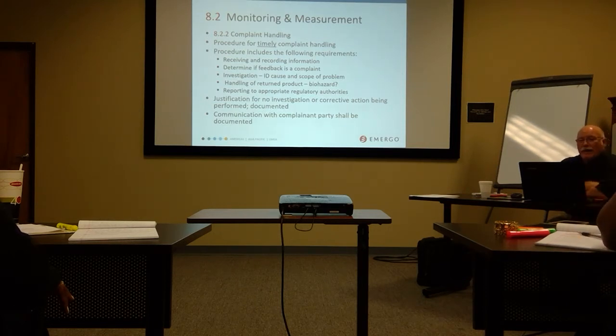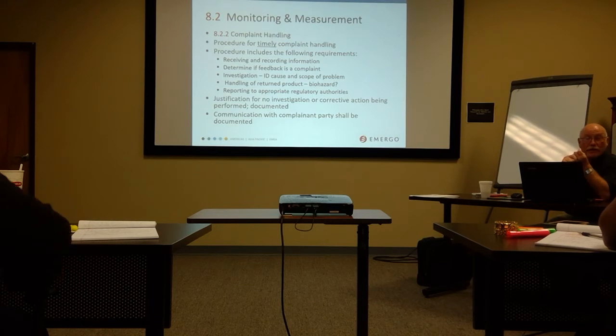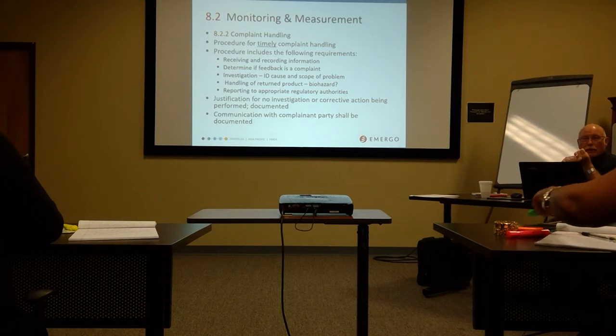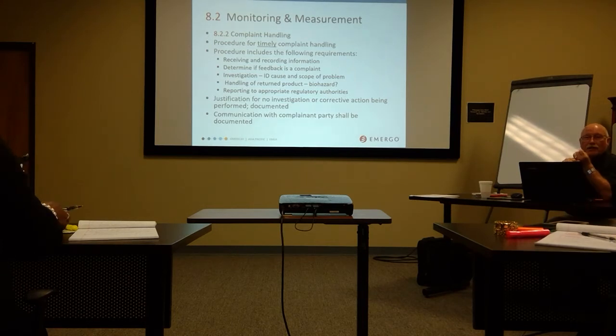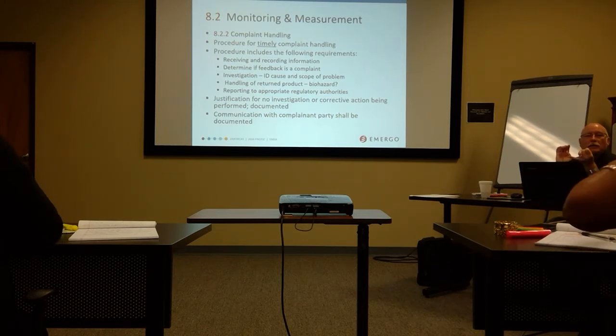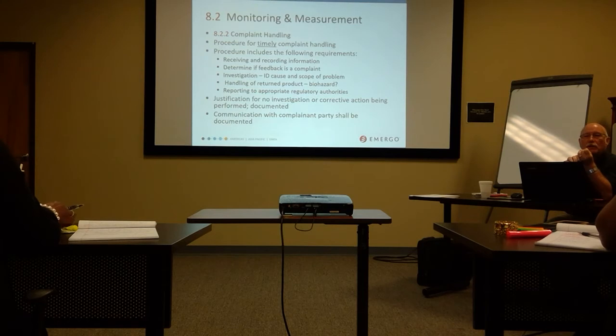So determine if feedback is a complaint. If it is a complaint, it goes through the complaint process. So in the complaint process, you should have a complaint form, electronic or hard copy, however, makes no difference. One of the things, assign this thing a complaint number. It's not a requirement, but good luck managing this process if you don't do it. Good practice and procedure should say, this is how we assign complaint numbers. This is the rationale for that.